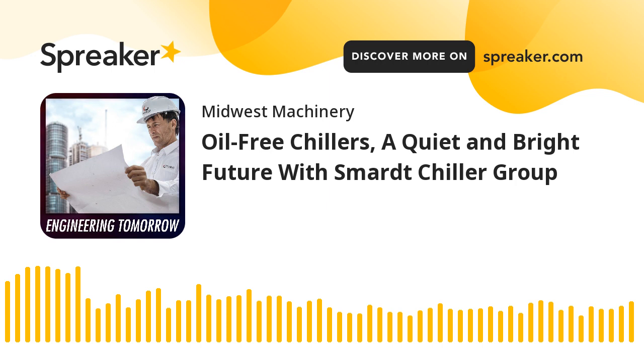What we call CPEX, our central plant optimized controller, basically advises the building automation system that's running the equipment where the set points need to be in order to achieve whatever demand requirements are being sensed and required. In doing that, it's looking at the equipment individually to see where the sweet spot of the towers, the pumps, and the chiller are in order to perform at an optimal level.